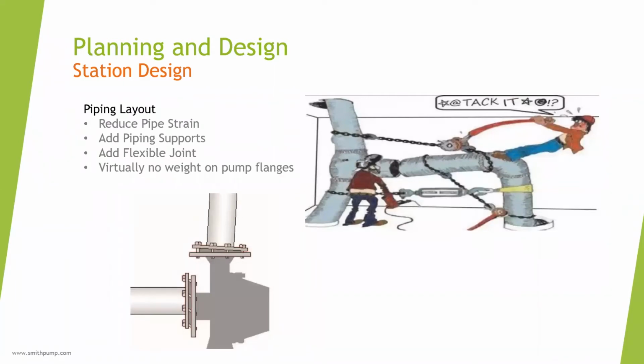The first way to distort the discharge head is pipe strain. Have you ever heard those dirty words mentioned before? It's when 2 pipe flanges that don't align are forced together. This can cause serious damage to the pump.